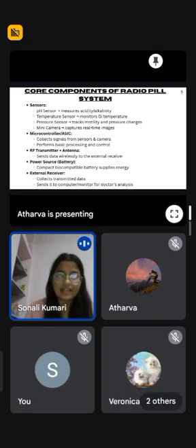Now the second component is the microcontroller or the ASIC. It collects the signals from the sensors and the cameras from inside of the body and performs basic programming and functioning. Then we have the RF transmitter plus the antenna, which sends data wirelessly to the external receiver.